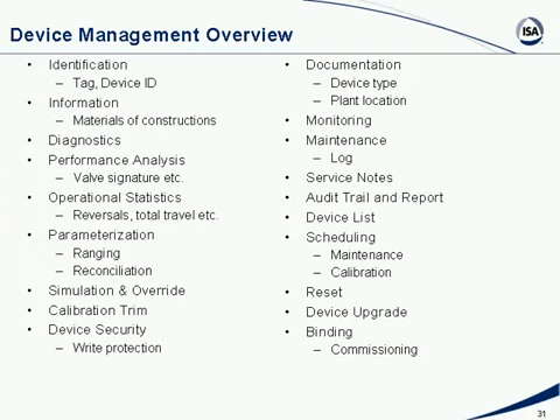Based on the results of diagnostics and so on, I can schedule my maintenance. Okay. If I have a failure or impending failure, I can schedule maintenance for that device. If I see that the performance of a device is degrading, I can schedule a calibration for that device in my Intelligent Device Management software. Oh, obviously I can reset the misbehaving device. I can upgrade the device by downloading new firmware, etc. And obviously the Intelligent Device Management software is also used for commissioning devices.